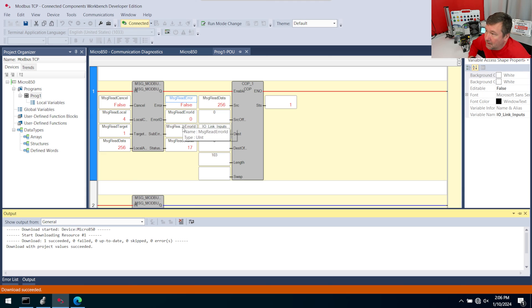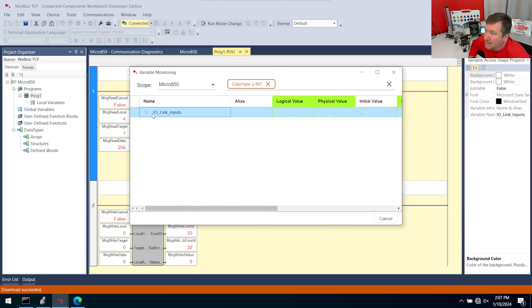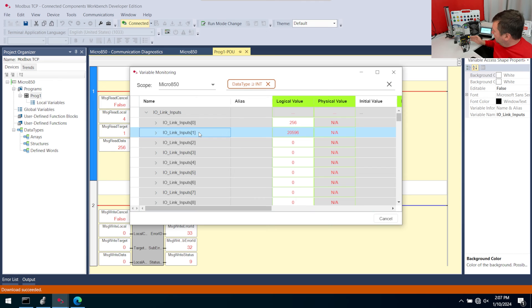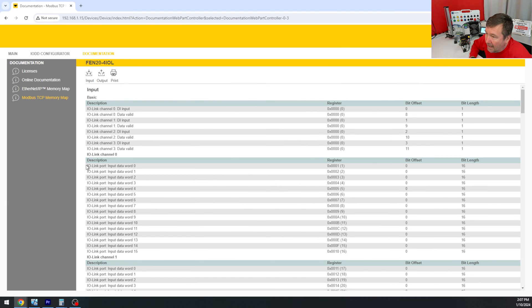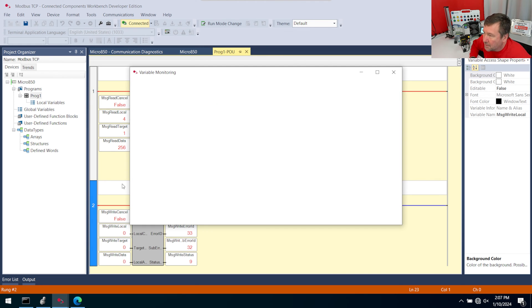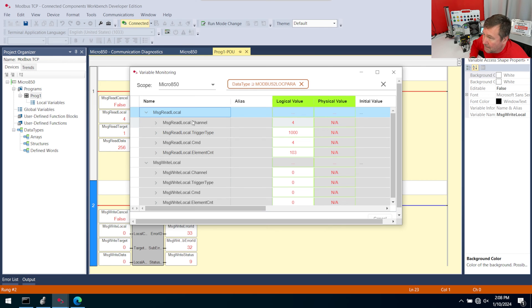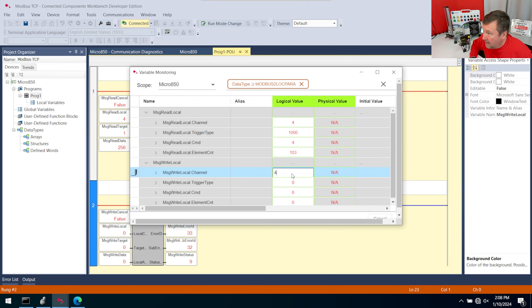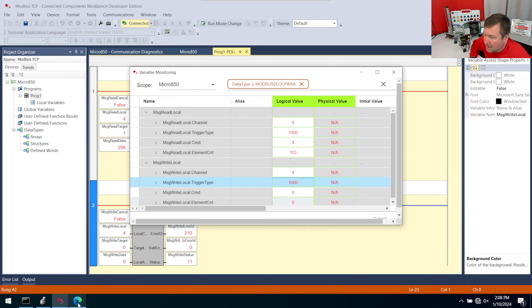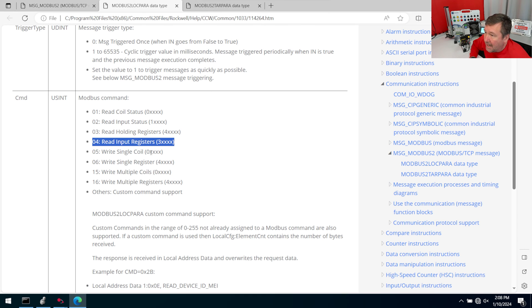That way you can get those address parameters back into that Modbus instruction. And very happily, we have no error here. But if we right click on IO link now and go to variable monitoring and we hit our arrow, so now word 1 changes when I stick my hand in front of the sensor. And that lines up with what our descriptions are saying in our Turck web browser. Now let's see if we can work on the write message. So we're going to start with the local parameters again. And we'll hit our arrow to open them up. In fact, let's go ahead and hit the arrow on the message read local because we may be able to reuse some of this. In fact, we can. And our channel is going to be 4 again because we're still going out the Ethernet.